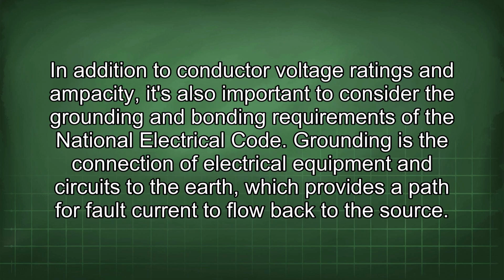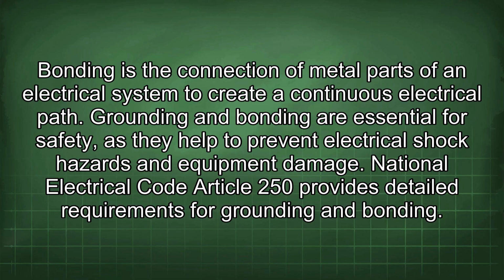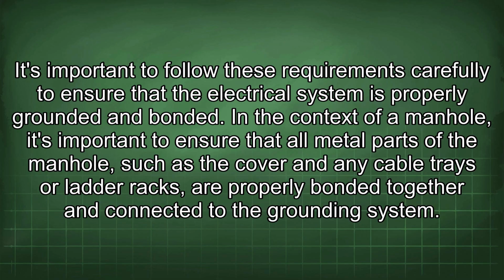In addition to conductor voltage ratings and ampacity, it's also important to consider the grounding and bonding requirements of the National Electrical Code. Grounding is the connection of electrical equipment and circuits to the earth, which provides a path for fault current to flow back to the source. Bonding is the connection of metal parts of an electrical system to create a continuous electrical path. Grounding and bonding are essential for safety, as they help to prevent electrical shock hazards and equipment damage. National Electrical Code Article 250 provides detailed requirements for grounding and bonding. It's important to follow these requirements carefully to ensure that the electrical system is properly grounded and bonded.